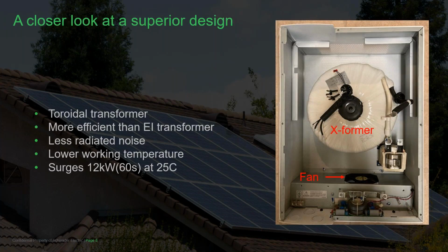XW Pro boasts an 80-pound toroidal transformer that gives it such a robust surge capability, which is 12 kW for 60 seconds at 25 C. Toroidal transformers are more compact, more efficient, and offer less noise than a standard EI transformer. Note the fan sitting just below the transformer. XW Pro monitors heat sink temperature and transformer temperature. In environments with higher ambient temperatures, use the derating chart in the manual to calculate your maximum continuous power in the warmest part of the year, unless of course the system is located in a controlled environment.